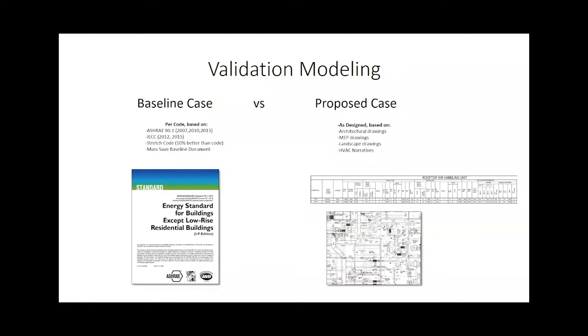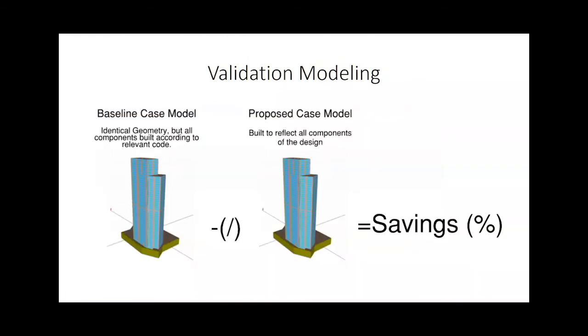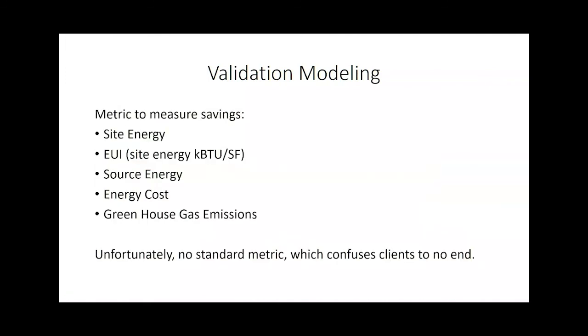So you end up with two models: one, the baseline, which is just code compliant, and your proposed case, which is your actual design. You then compare those two models. You either subtract your proposed case from your baseline case to get total energy savings, or divide your proposed case into your baseline case to get your percent energy savings.